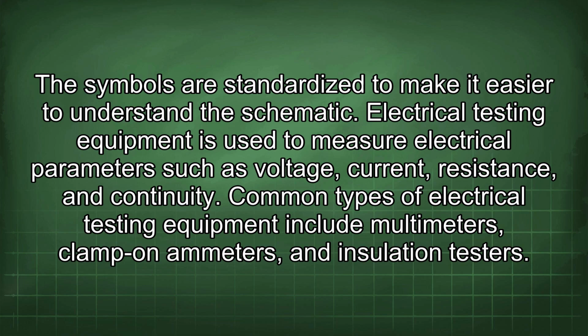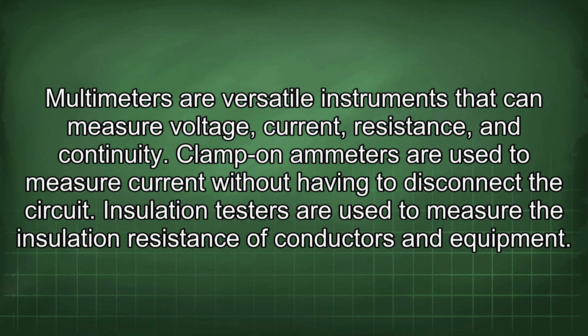Electrical testing equipment is used to measure electrical parameters such as voltage, current, resistance, and continuity. Common types of electrical testing equipment include multimeters, clamp-on ammeters, and insulation testers. Multimeters are versatile instruments that can measure voltage, current, resistance, and continuity. Clamp-on ammeters are used to measure current without having to disconnect the circuit. Insulation testers are used to measure the insulation resistance of conductors and equipment.